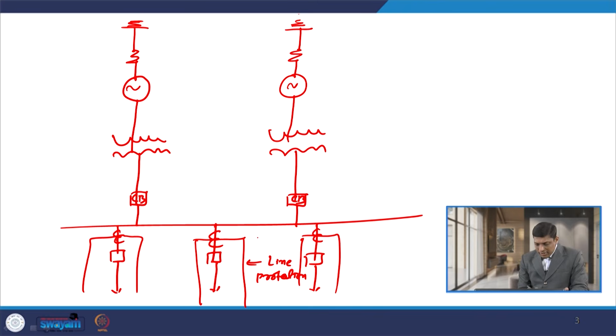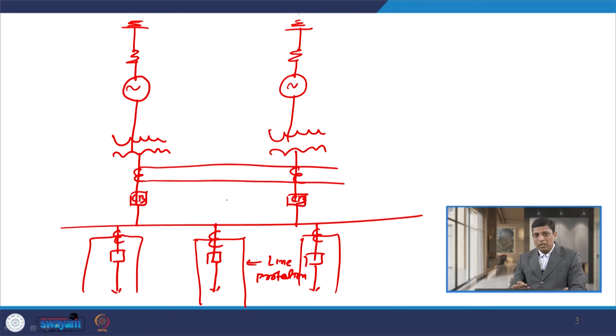Now, if I consider another device, let us say the bus bar, then we have to overlap the bus bar protection zone. So, we can put the CT somewhere here, let us say I put the CT for the bus bar here and I connect these two on this side, right. Now, on the line side, where do I have to put the CT, on the upper side or the lower side of this line CT? If I put it on the upper side of the line CT, then the line and bus bar zones are not overlapped. So, I put the bus bar CT somewhere here on this side below the line CT and I connect it like this. So, then the bus bar relay is connected here. So, the bus bar protection zone and the line protection zone are both overlapped.